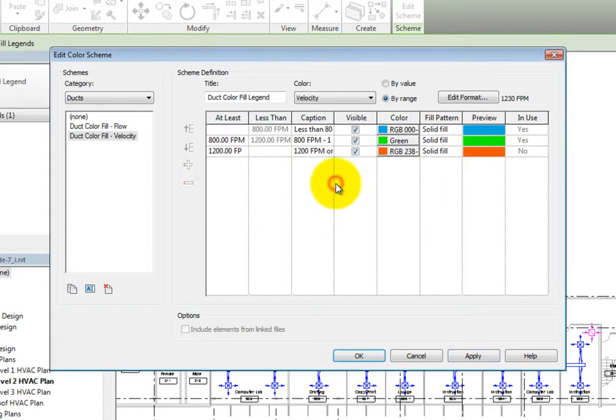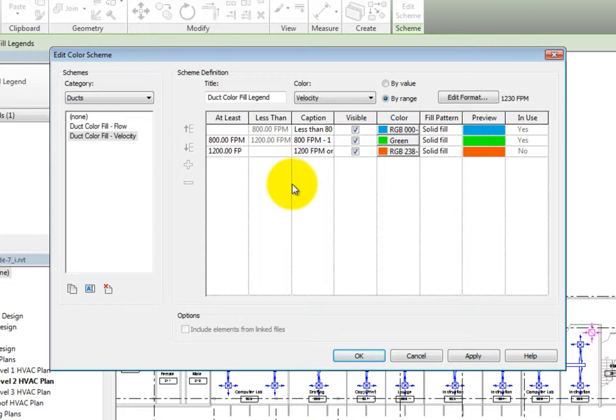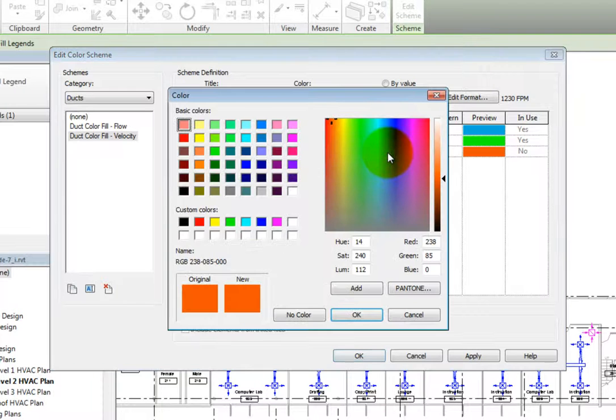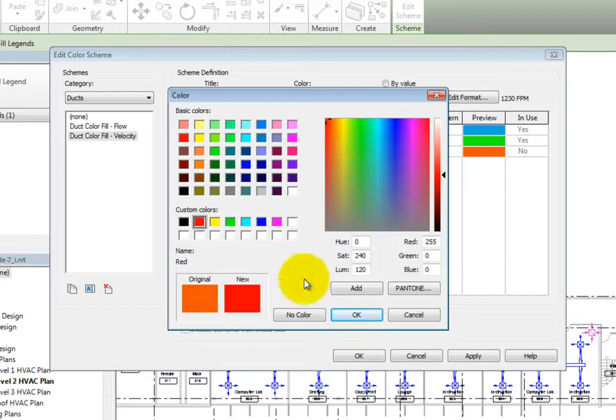Now I can use these values. I really do not need any of the ductwork to have a velocity greater than 1,200 feet per minute, or 6 meters per second in the metric file. So I'll click the button in the color field for the last row to open the color dialog. Then I'll change the color to red and click OK.